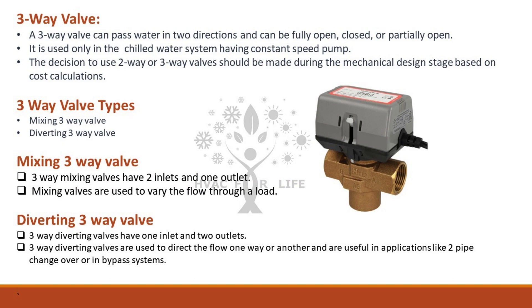A three-way valve can pass water in two directions and can be fully open, closed, or partially open. It is used only in chilled water systems having a constant speed pump. The decision to use two-way or three-way valves should be made during the mechanical design stage based on cost calculations.